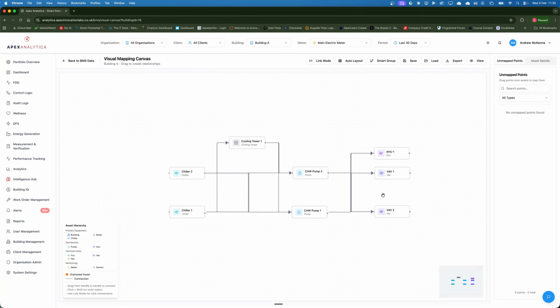A typical engineer, when it's really warm in an office, gets a call out, comes to site, pops his head above the ceiling, checks valves, maybe on a fan coil unit, sees the valves are operating okay, sees the fans running okay, then has to go and maybe check a zone valve somewhere in the ceiling, moving those ladders. He then figures all of this out from endpoint all the way back to root cause, which might be a 3-port valve that's maybe stuck in a plant room or whatever it would be.